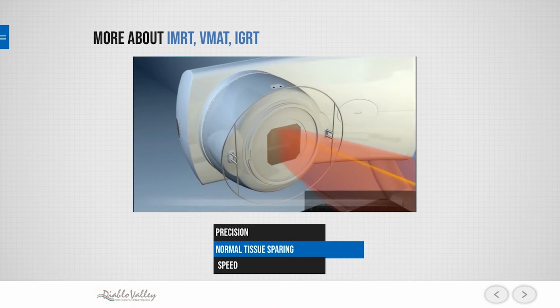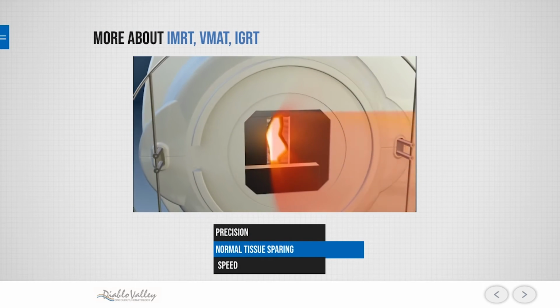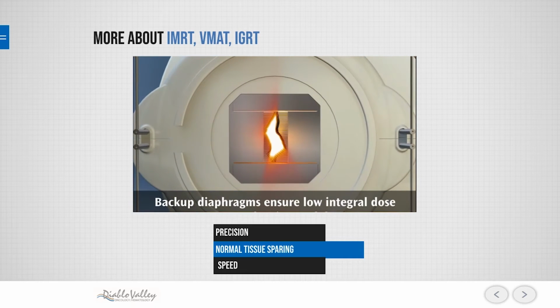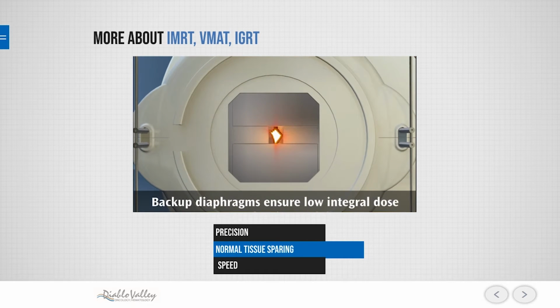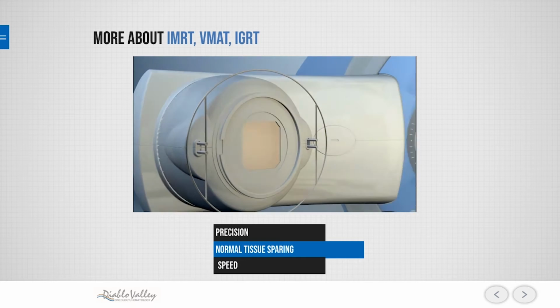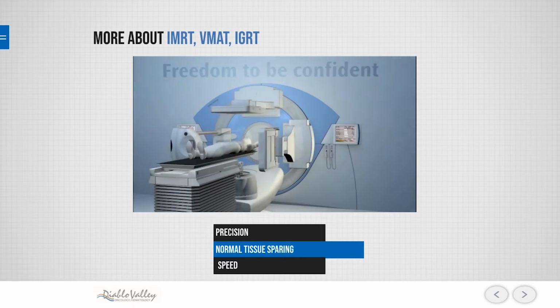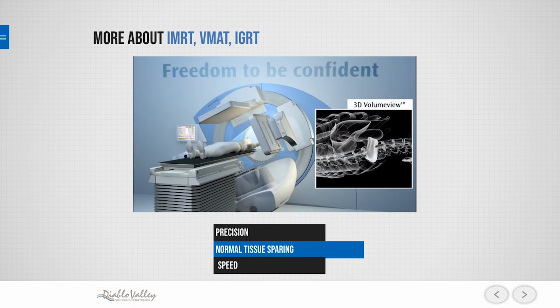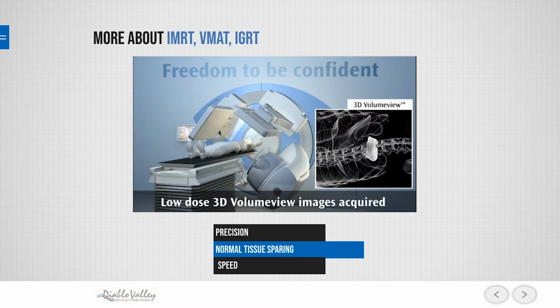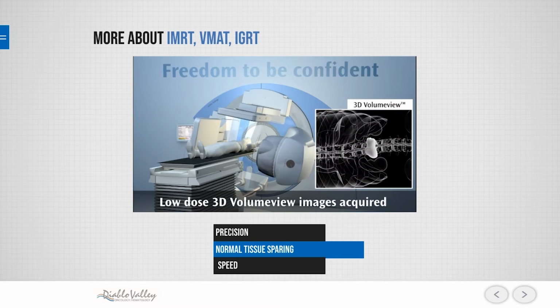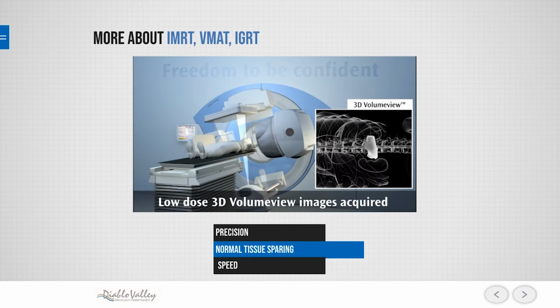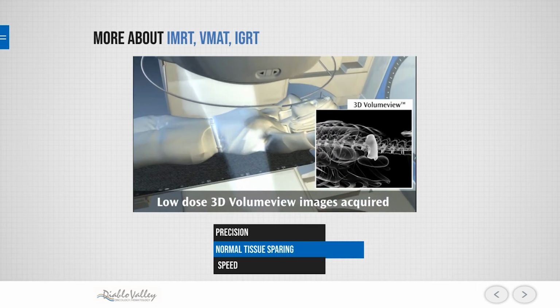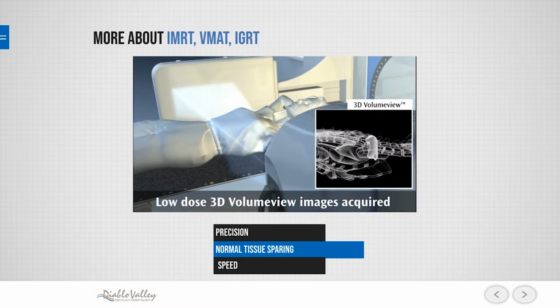This is a quick video to demonstrate two of the other acronyms that we talked about, volumetric arc therapy and IGRT. So that's the head of the machine. You can see that we can dynamically move the leaves, we can dynamically move the jaws and modulate the field in real time. As I said before, typically we would leave the fields in a static position and we would treat 5 or 6 of them per treatment. Now we utilize the fact that the machines can rotate and that we can in real time change the leaf position as it rotates to do something called volumetric arc therapy, which I'll show in a minute.